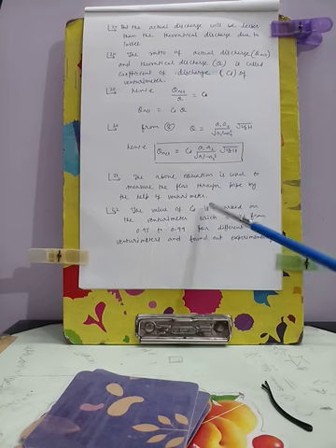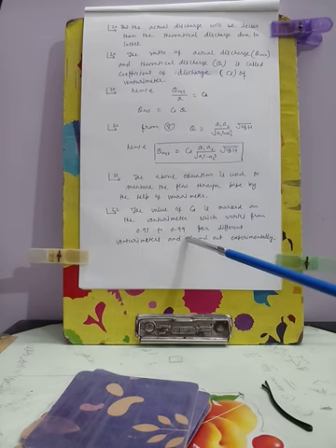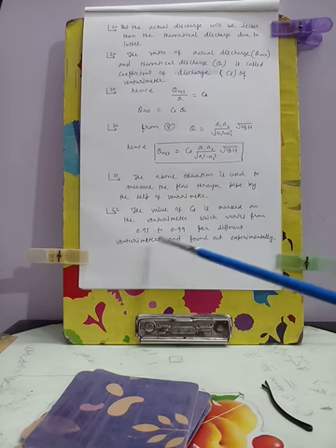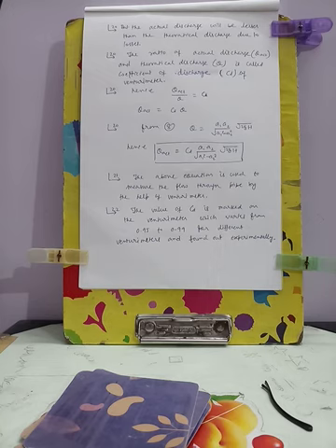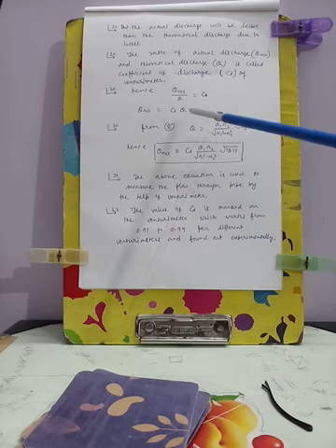Generally the value of CD lies between 0.95 to 0.99 for the various venturimeters. So in this way we can find out the equation for venturimeter flow.